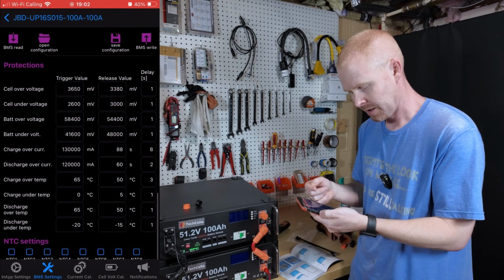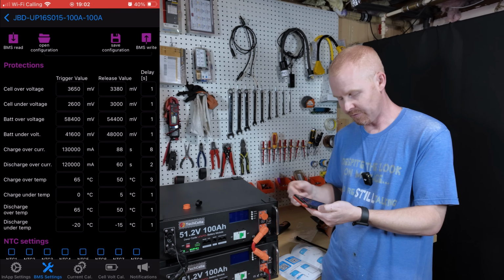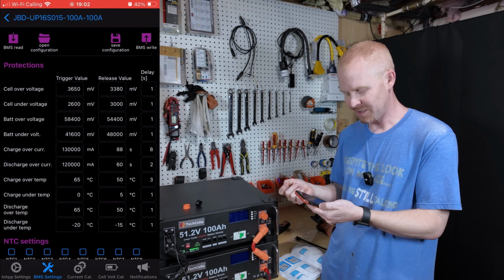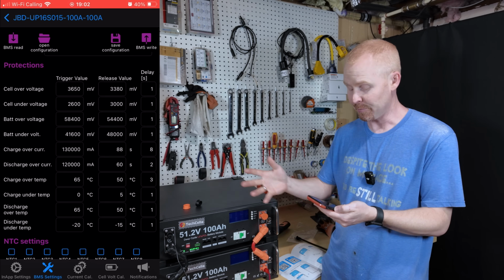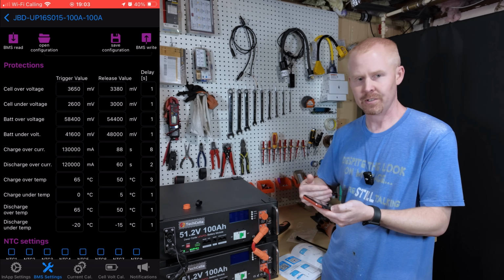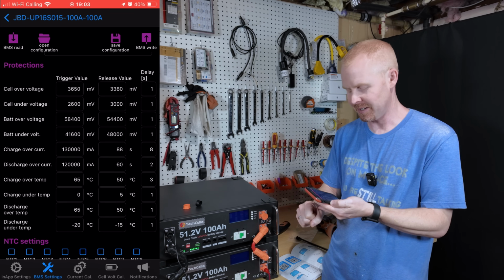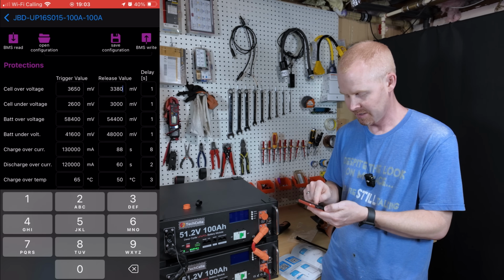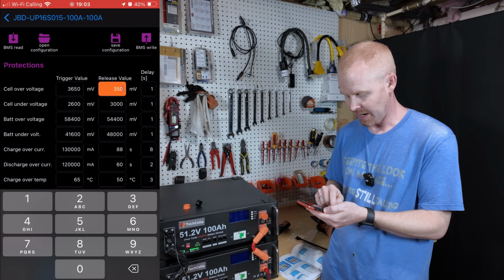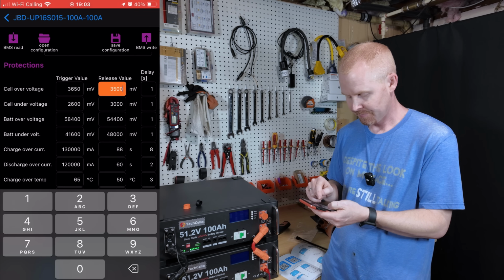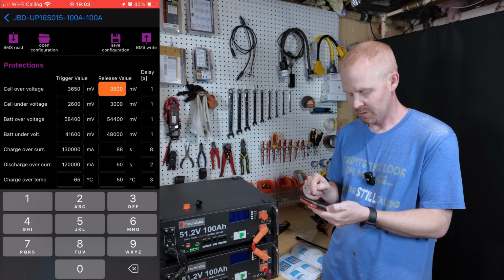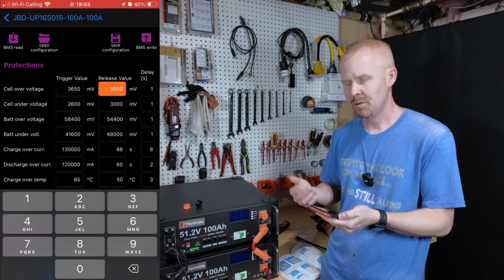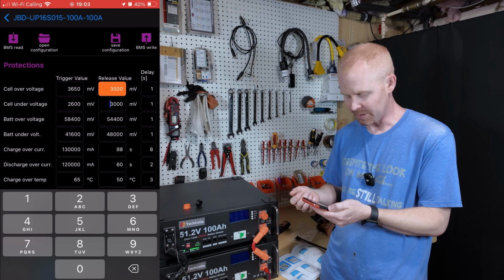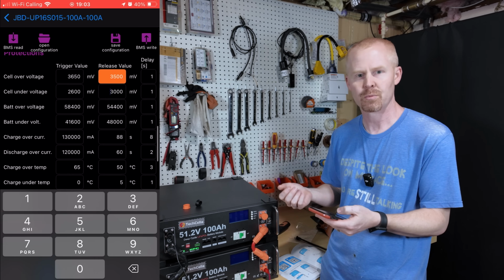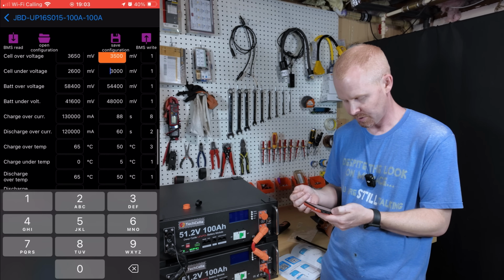Protection values: cell over voltage 3.65 volts. The release is 3.3 - that's a big gap for a release. It almost seems like you're never going to balance out if you've got that big of a gap for the release. I'm actually going to change that to 3.5. The cell under voltage is 2.6 volts. You could do a 2.8 for the under voltage, I guess, but I'm less concerned with that one than with the over voltage.